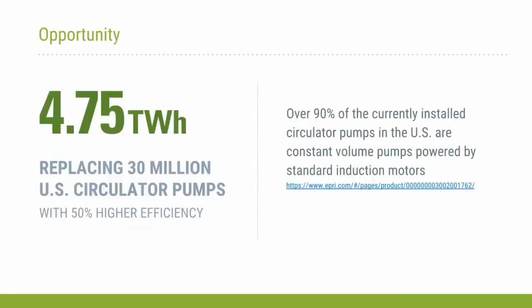Okay, next slide. So really quickly, we're going to walk through the opportunity for these small circulator pumps. As Jay mentioned, there's about 30 million of them that are estimated to be in operation in the United States. The estimated energy efficiency gains from replacing those is estimated at over 50%. And I think one of the interesting notes here is that over 90% of the currently installed circulator pumps are the older constant volume pumps with standard induction motors. And we'll get into the details on the next slide of what a circulator pump is. But at a high level, the main takeaway here is that there's a very large opportunity throughout the United States. And to date, only a small number of those have been retrofitted with these high-performance circulator pumps. Okay, next slide.